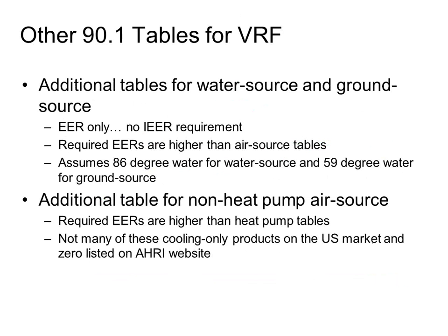You will also probably want to know, just as a discussion, I didn't bother putting the screens on here because I didn't want to confuse anybody with what needs to happen, but if you're doing a water source job instead of an air source job, then the tables are completely different than the ones I just showed you. There's a separate table for water source VRF systems, and yet another table for ground source systems. The water source requirements have higher efficiency requirements than air source, and the ground source has higher than water source. It's kind of the way it goes. Very similar to the chiller guys, right? There's certain air-cooled chiller rules you've got to hit, and if you have a water-cooled chiller, they give you a harder target to hit, just the way it goes.